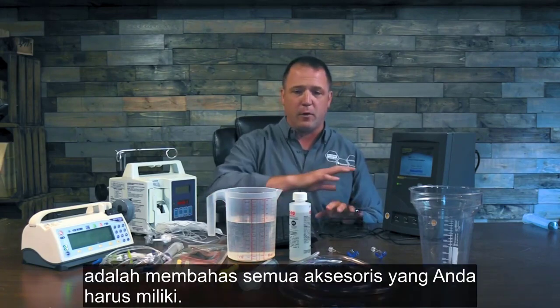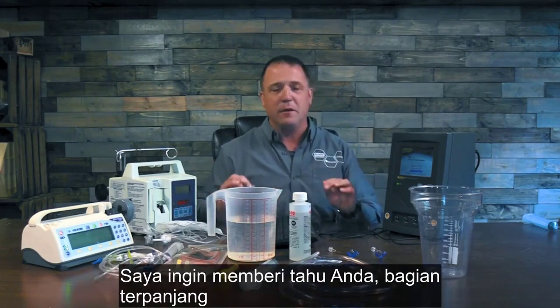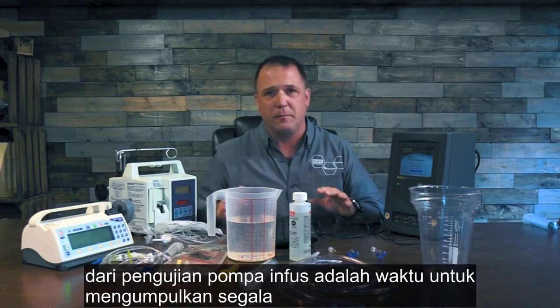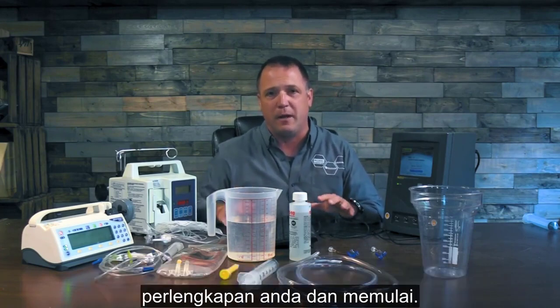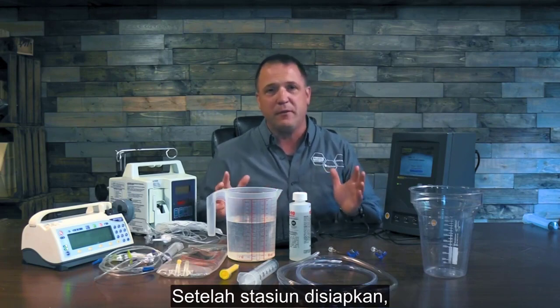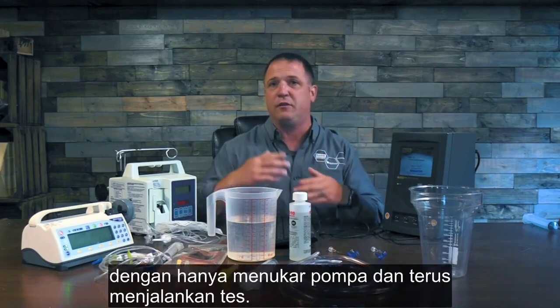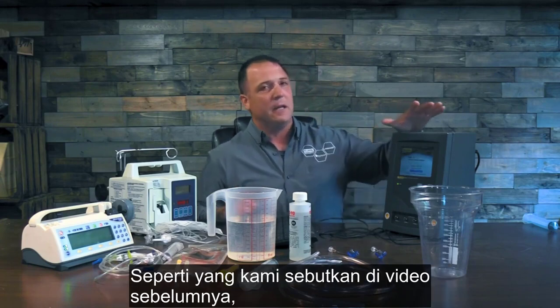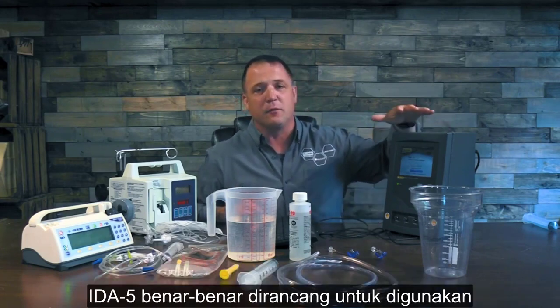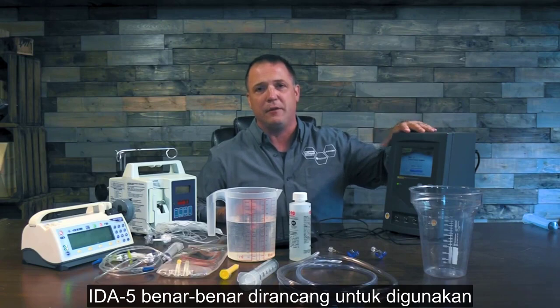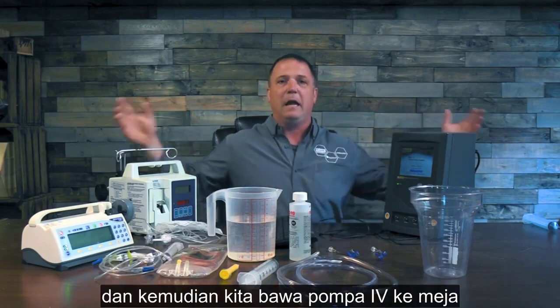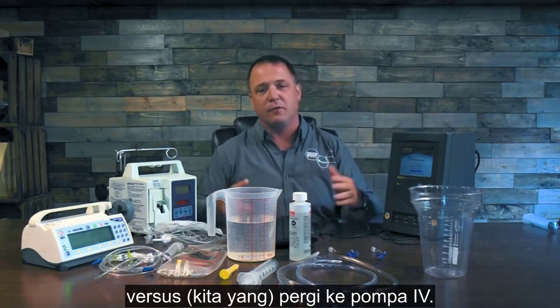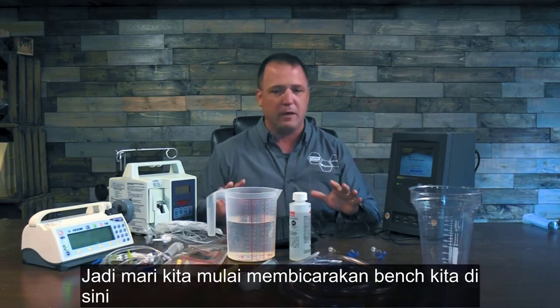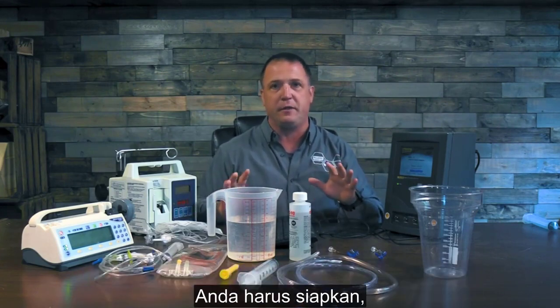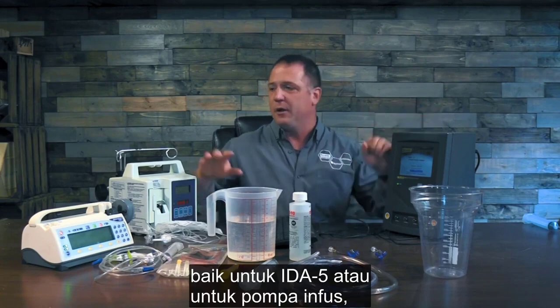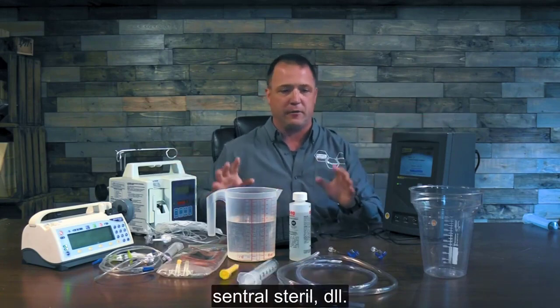The first thing we're going to do is go over all the accessories you're going to need to gather. I want to tell you the longest part about infusion pump testing is probably gathering up all your supplies and starting. After you've had your station set up, it's real easy to continue to just change out pumps and keep going. Like we mentioned in an earlier video, the IDA-5 is really set up for that desktop application where we're going to establish a test bench and then bring the IV pumps to it versus going out to the IV pumps. So let's start going around the bench here and talking about the accessories you're going to need to gather, either from the IDA-5 or from your infusion pump, central sterile, etc.